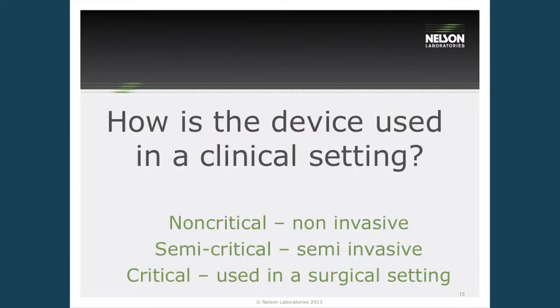So first we need to determine how the device will be used in a clinical setting. So is this device a critical, semi-critical, or non-critical device? These are Spaulding classifications that you can find pretty much in any guidance or regulatory document, but it determines kind of what residuals we should test for and how we should perform the cleaning validation.